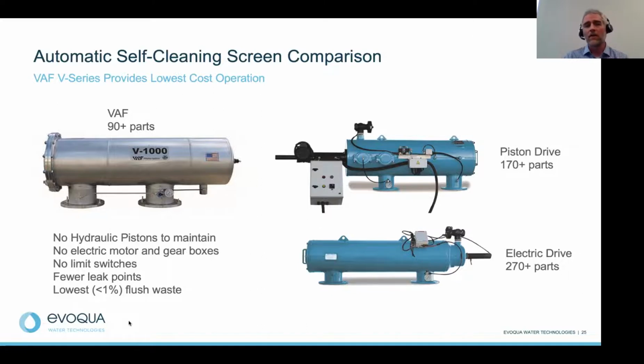VAF provides really the lowest cost of operation out today. No hydraulic pistons to maintain, no electric motors or gearboxes to maintain and or potentially change out for failure, no limit switches to constantly manipulate and maintain. And because you don't need those technologies, there are fewer levels of penetrations, ultimately providing fewer leak points. That ultimately could be a safety hazard for some of your operations staff. And with our bidirectional screw and water motor, our patented technology, we are very capable of very effectively controlling the cleaning cycle. So you are removing those particulates at the highest level of degree every time.